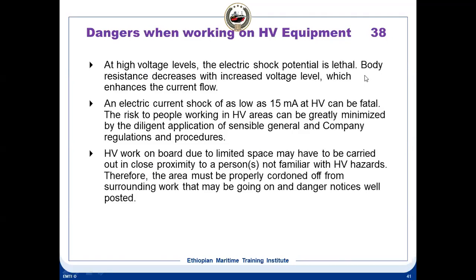For shock, your body resistance will decrease with increasing voltage. An electric current shock as low as 15 mA at HV can be fatal. The risk to people working in HV areas can be greatly minimized by diligent application of sensible general and company regulations and procedures. So that is the reason that on high voltage equipment, you cannot just open the equipment like that.